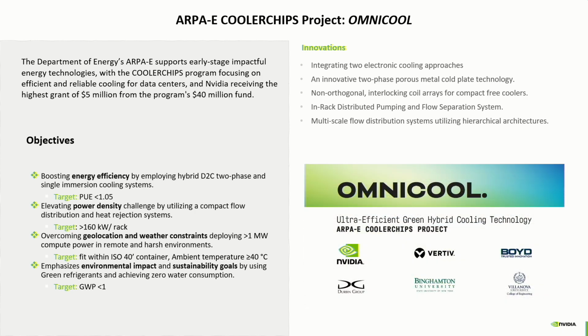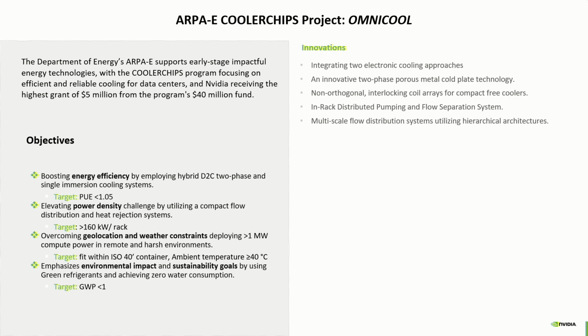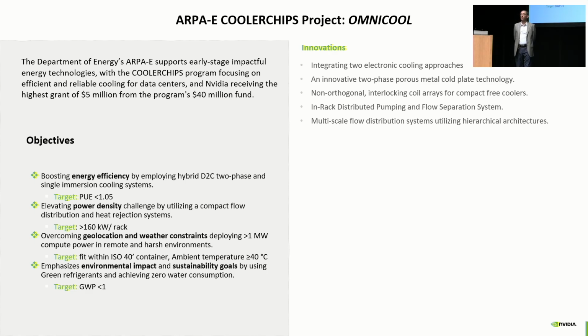In summary, a 1 megawatt data center in a 40-foot container, PUE less than 1.05, no fans, and that's a conceptual design with two-phase direct-to-chip cold plates and immersion inside of a tray. So another project we're working on at NVIDIA is basically a research project with the Department of Energy, ARPA-E, and that's the sort of thinking that we want the industry to think about. Think outside of the box. These racks are going to go to higher densities. We need to have solutions, and we're working with all of you to achieve that solution. Thank you for your attention.